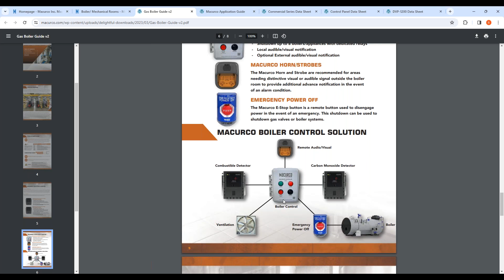So there is a boiler controller, which you will see right here on the top left, that we have built as a system. You tie your CO detector in there, and honestly, it's a reset box with a bunch of relays inside. And what we're doing is, once this detector hits that threshold, we shut the boiler down, it's latched. The end user can go in and reset the system. And in the event that it goes into that same alarm status again, then they know there's an actual carbon monoxide leak. It's not just a whim or a false alarm or anything of that nature.